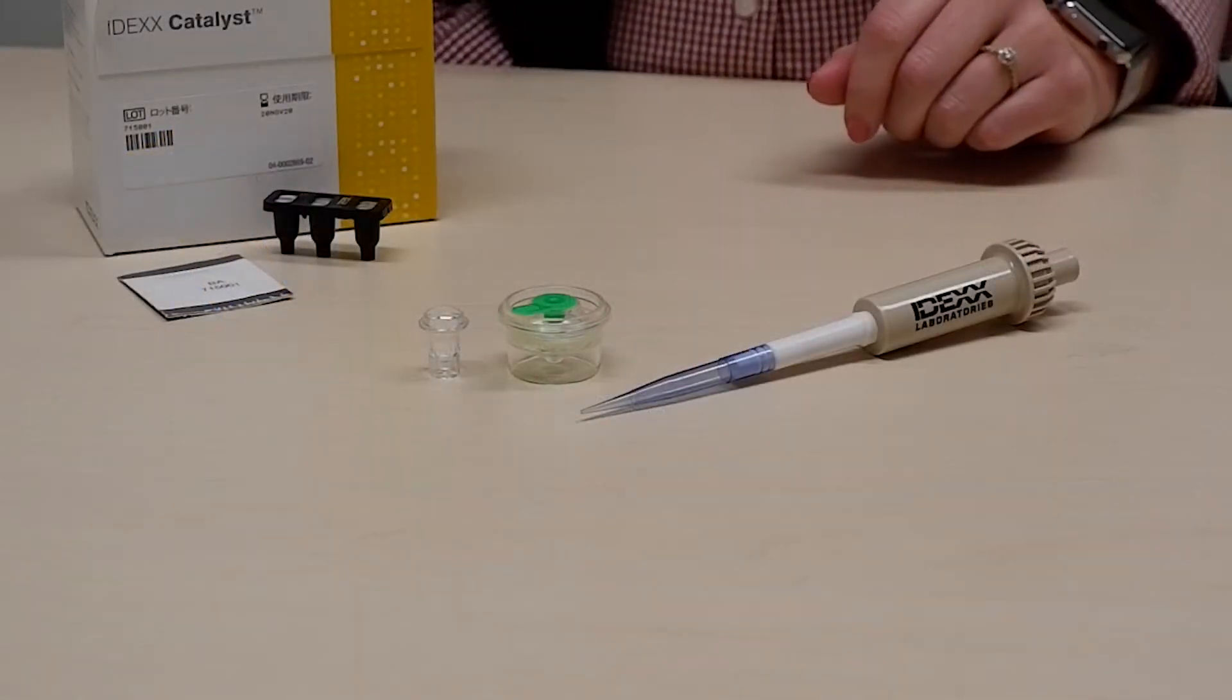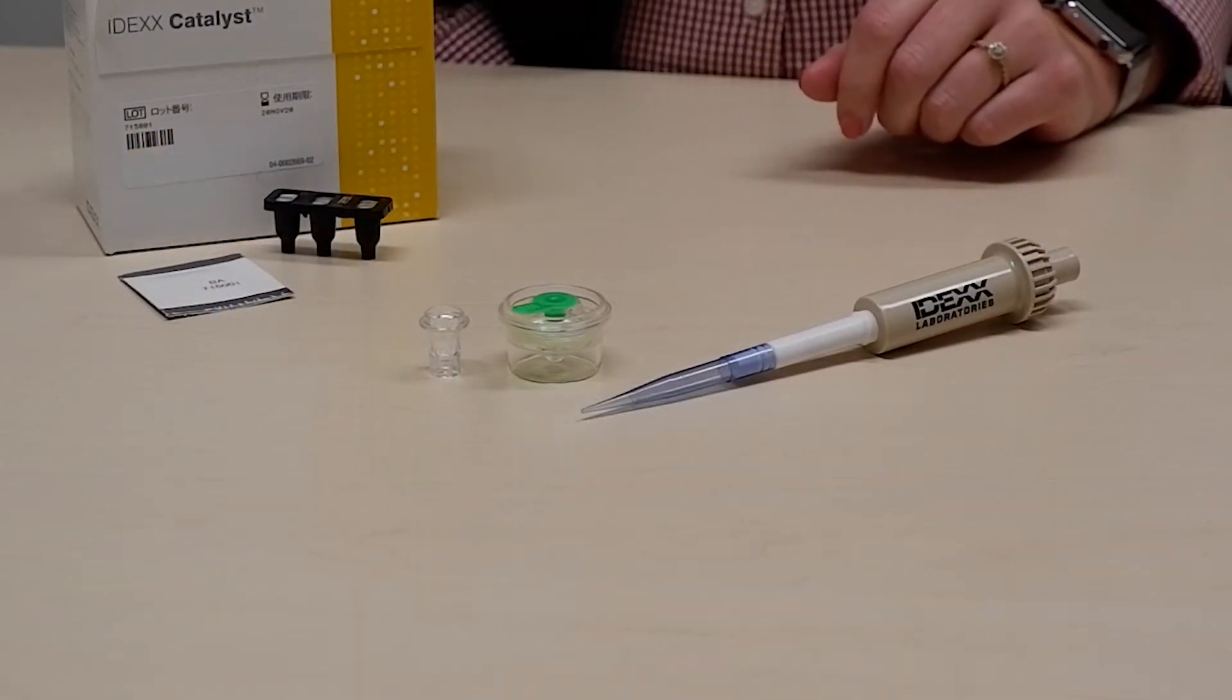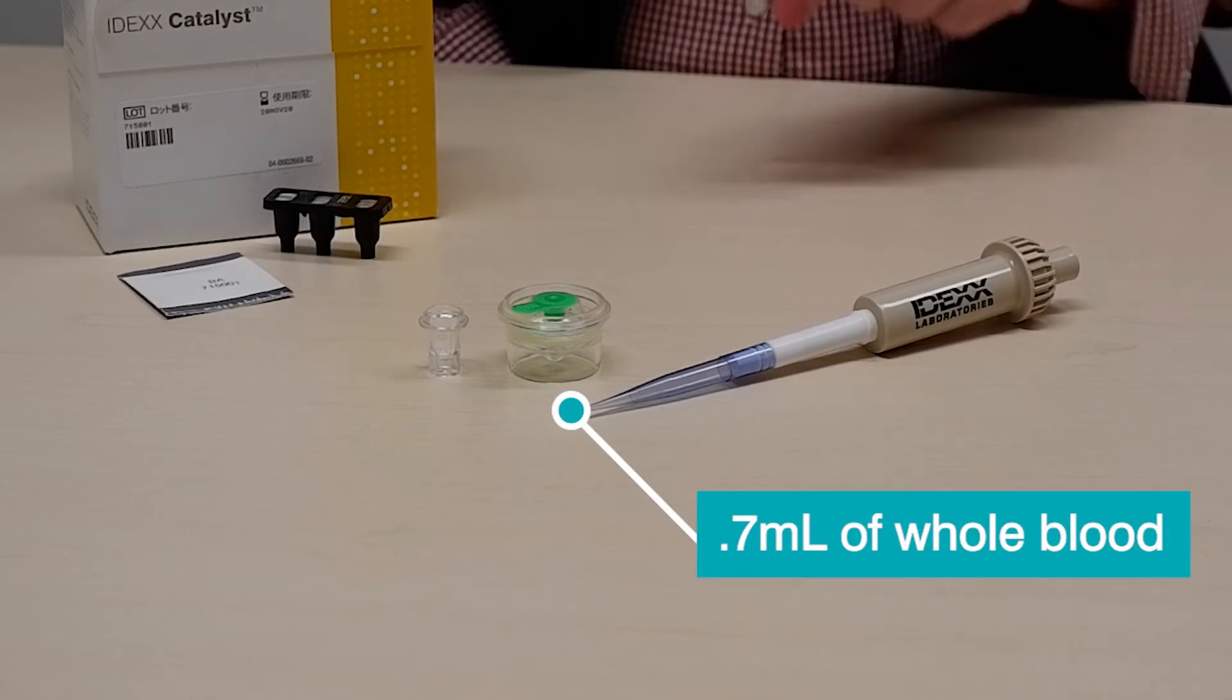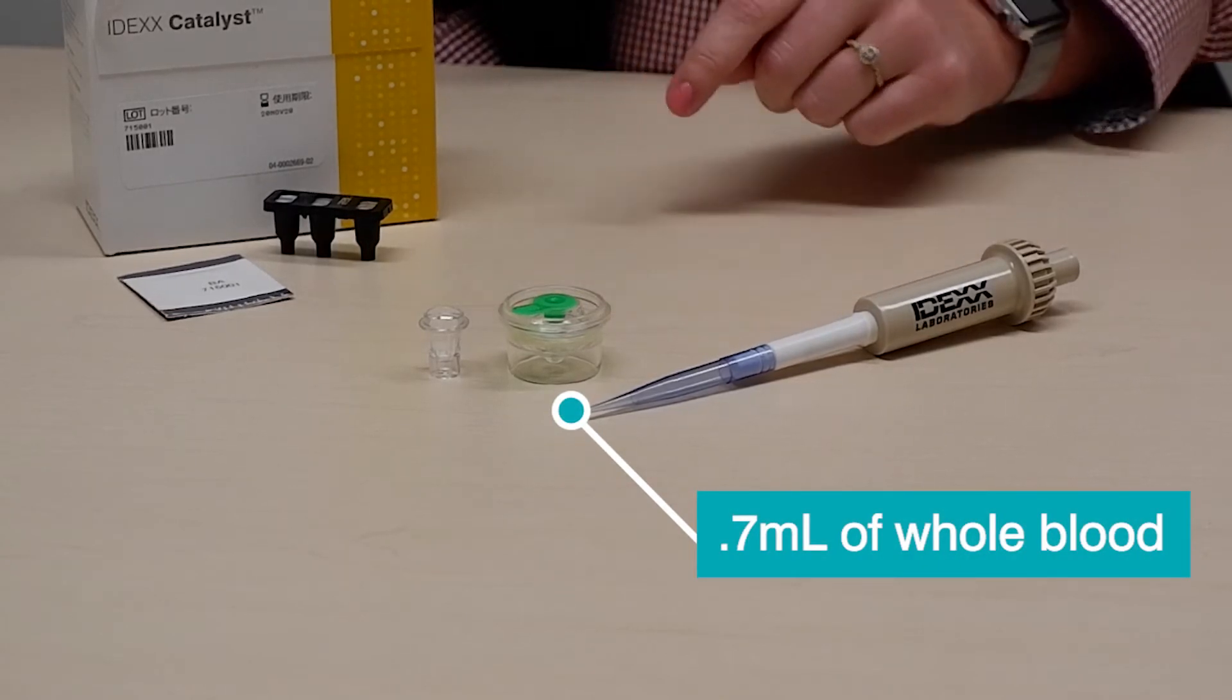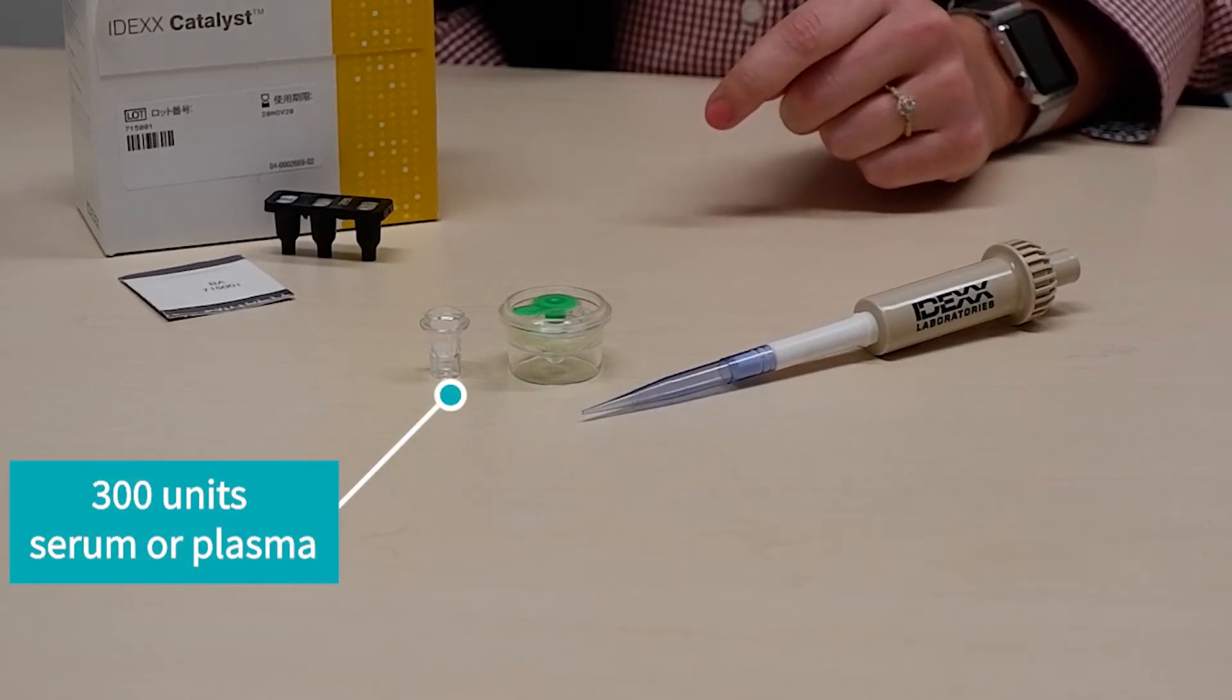The IDEXX Catalyst bile acids test can be run with 0.7 mils of whole blood using a lithium heparin separator or 300 units of serum or plasma using the sample cup.